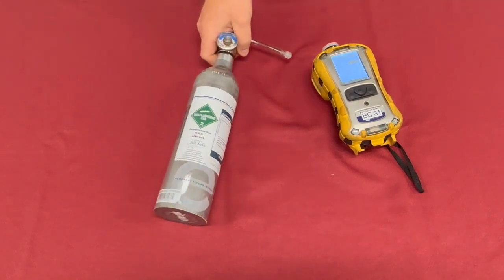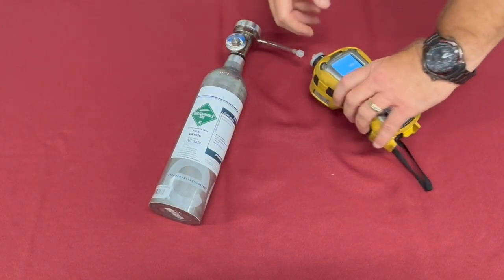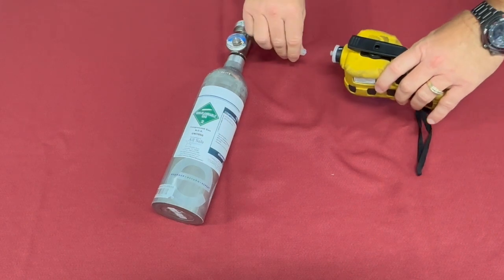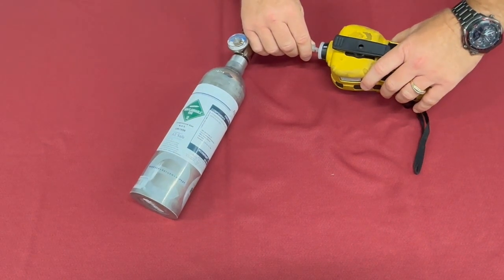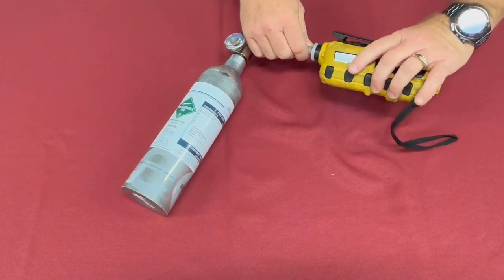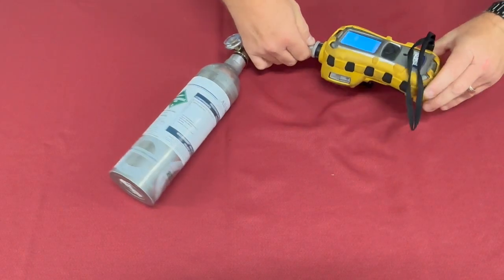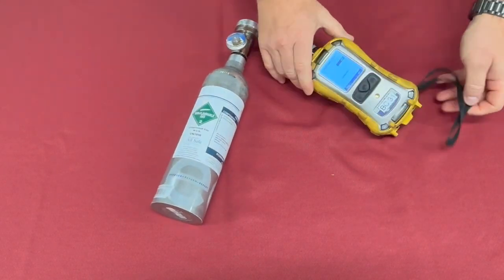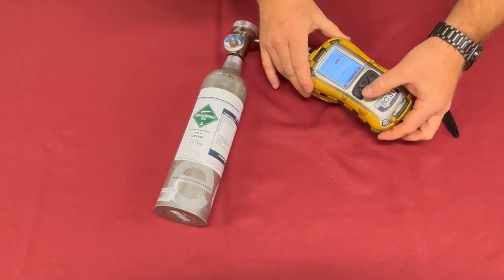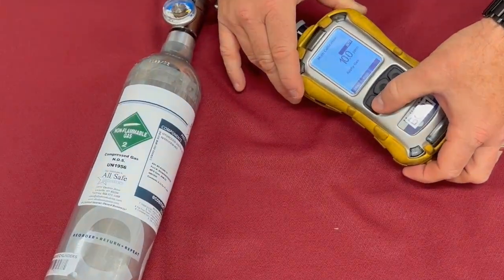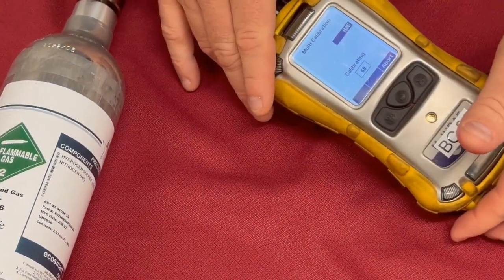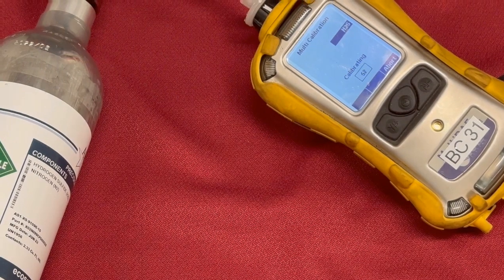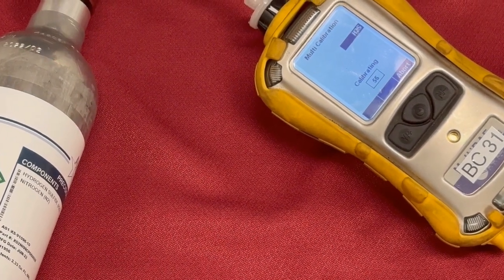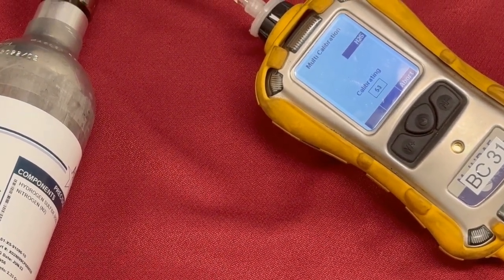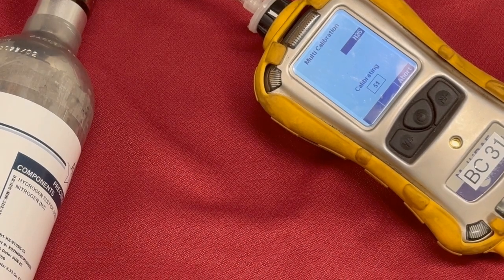So we hook this up in exactly the same way. We'll turn the meter over, bring it up to the port, and twist on till it's like that. And then we'll want to hit calibrate yes, start. You'll see this one only lasts 60 seconds. That's because we don't have that long soak time that's required for the hydrogen cyanide sensor.